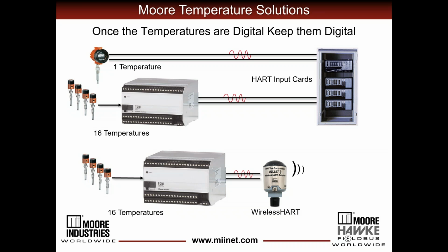Now, if you put a temperature transmitter or remote I/O near your sensor, the device digitizes the temperature measurement. If you then send the signal back to the control or data acquisition system via 4 to 20 milliamps, you end up creating 2 more errors. There is a digital to analog error creating the 4 to 20 milliamps in the transmitter. And then at the receiving device, there's an analog back to digital error, because the controlling device or the data acquisition system uses the digital signal. HART protocol is digital, and that's one way to avoid the conversion error.